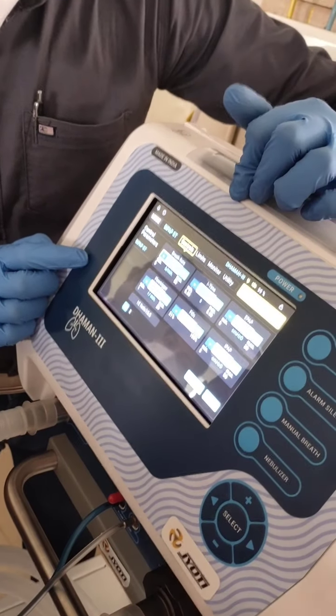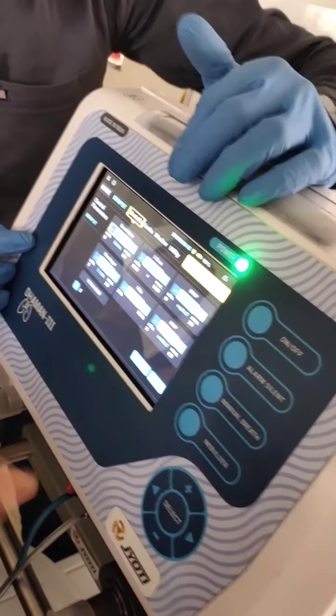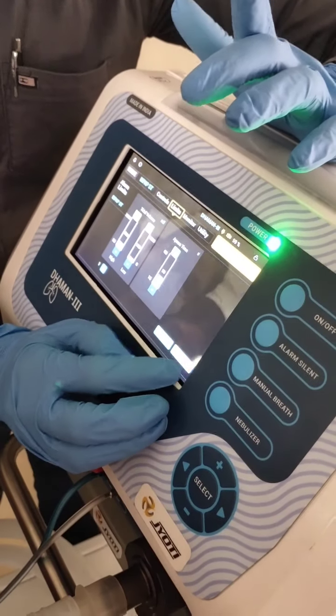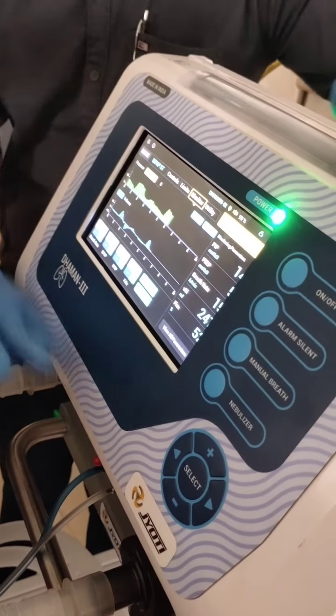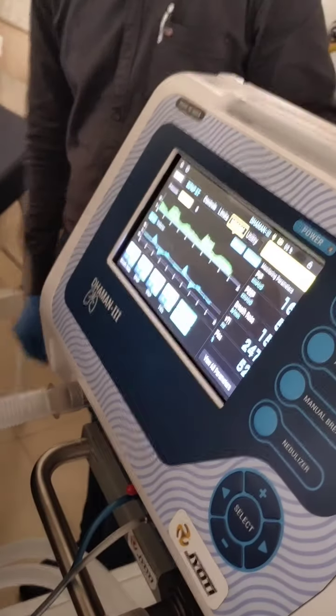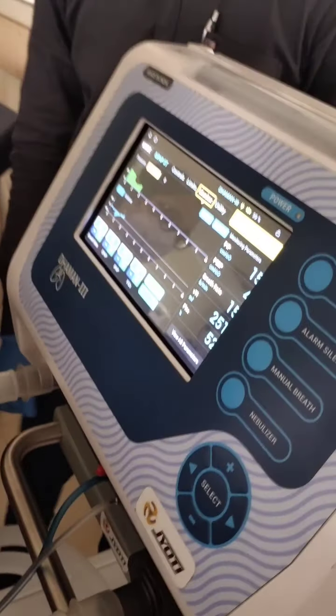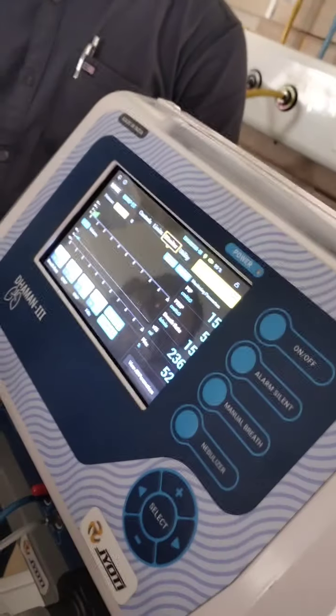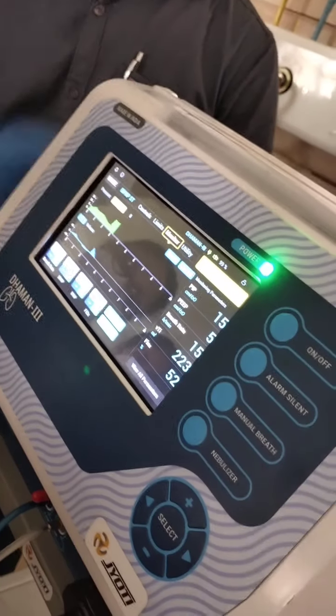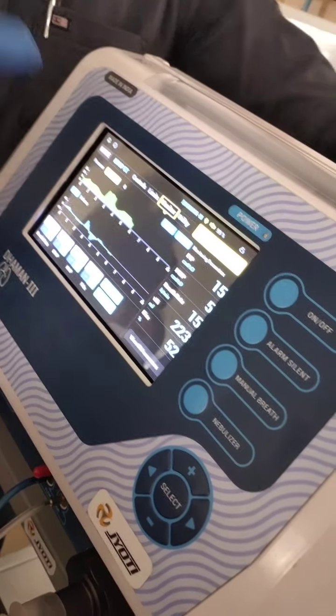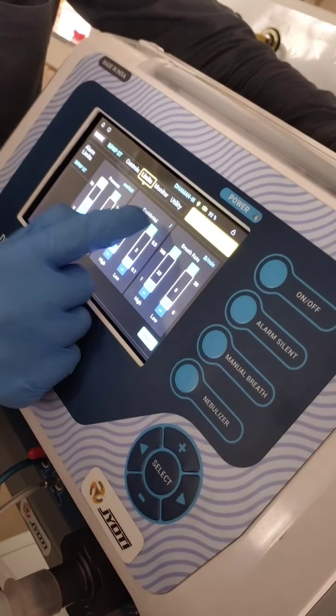Pressure settings. What now? Pressure settings are separate for IPAP and EPAP. Yes, ma'am, we have them on the page. Yes, IPAP and EPAP, 15 and 5. You have to change 15 to 10 and 5 to 2. It will change, you can do it. What's the difference? In CPAP the same pressure is for both inspiration and expiration. Here it's a varying pressure, separate for inspiration and expiration. If I increase that expiration pressure, what will happen? I will tell you. Okay, the limit I am putting at 4 now.